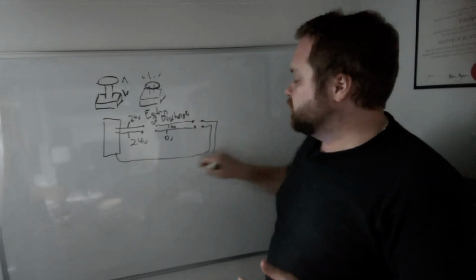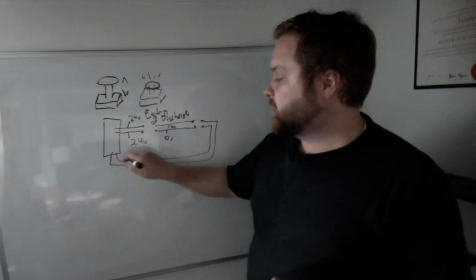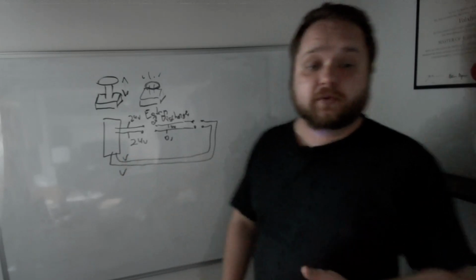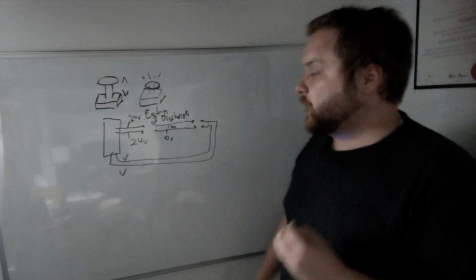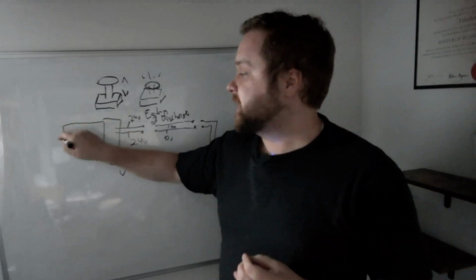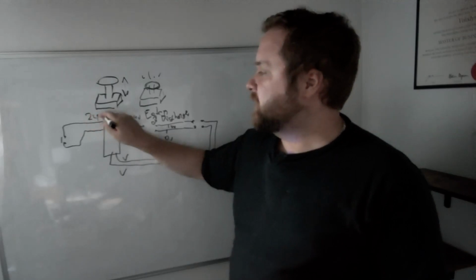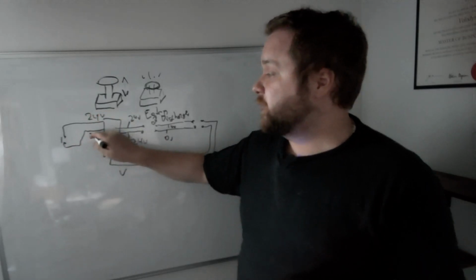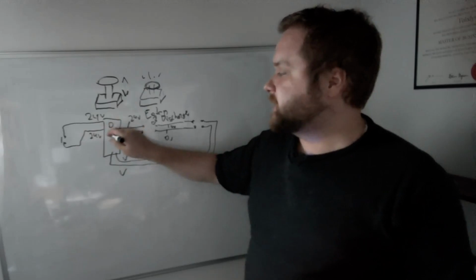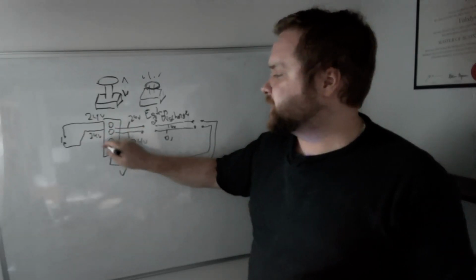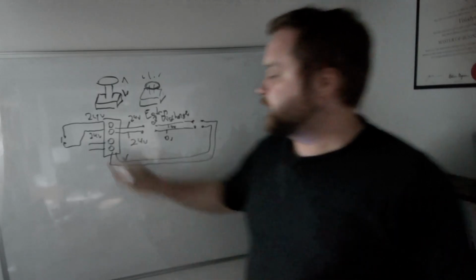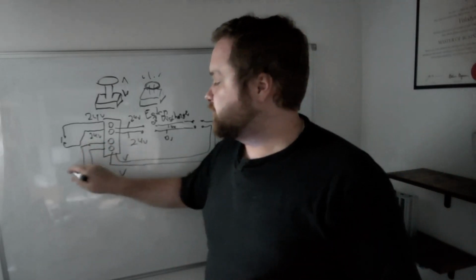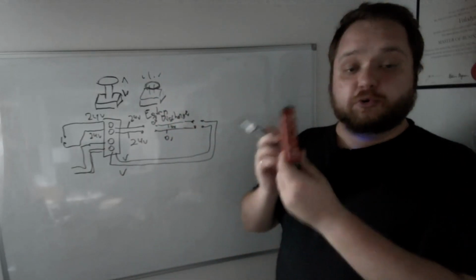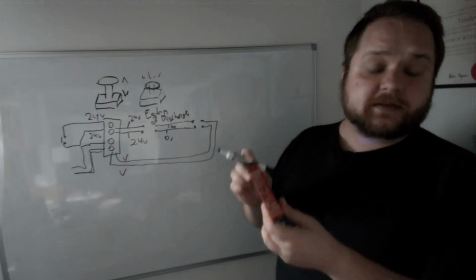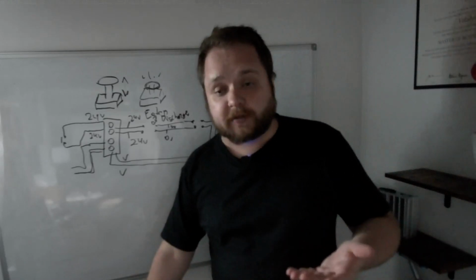And then once you complete the circuit, right? So you've confirmed that here you have 24 volts and here you have 24 volts. In most cases, the relay will require a reset signal. So again, of course, if you have 24 volts here, and then when you press the button, you also need to have 24 volts. And this is going to energize both of the channel outputs. So again, this is going to be different LEDs depending on how this looks, but your safety circuit is going to show with LED status indicators that everything is looking good. And like I said, this is going to be varying based on the specifics, but ultimately that is the base case scenario.